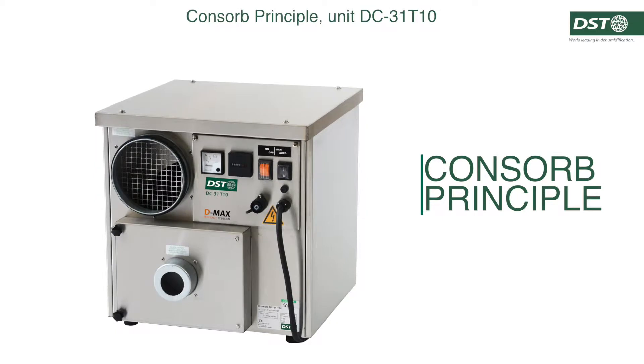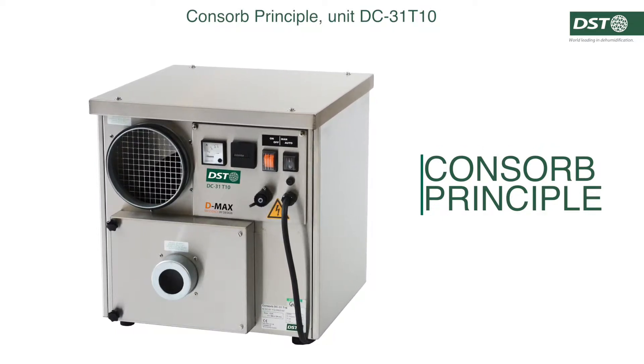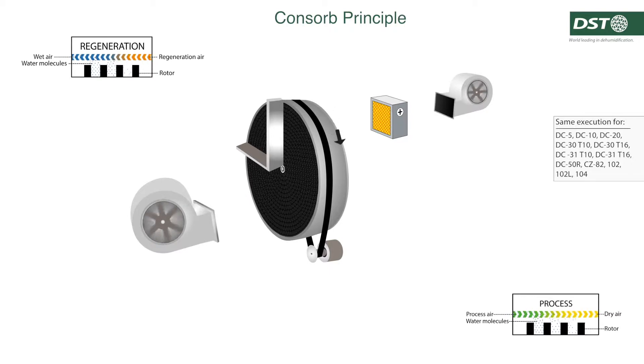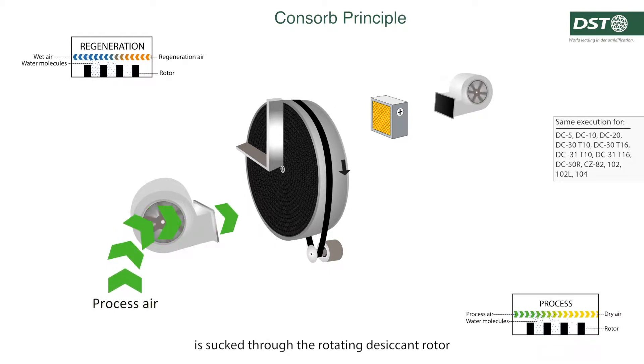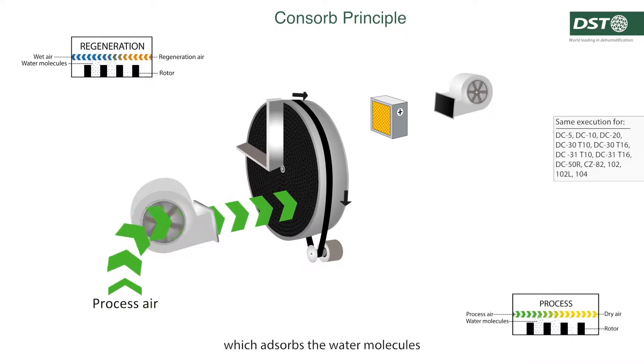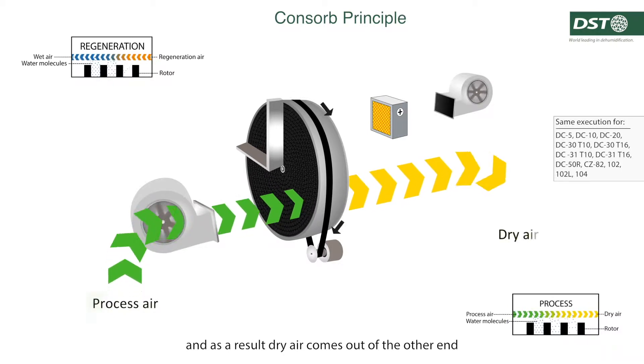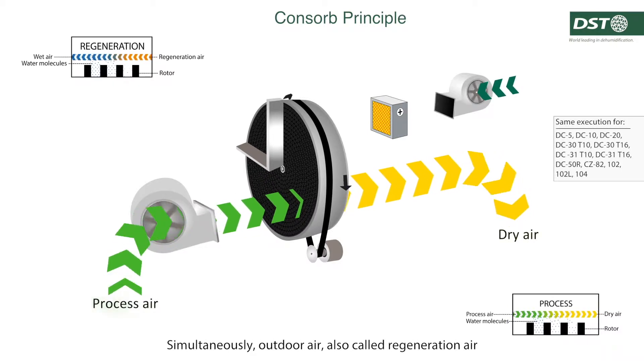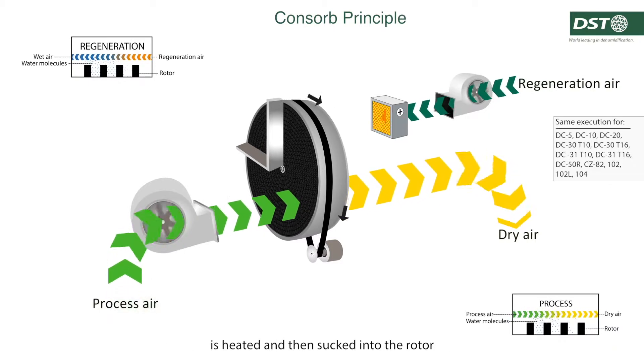The desiccant principle: humid air, also called process air, is sucked through the rotating desiccant rotor, which adsorbs the water molecules. As a result, dry air comes out of the other end.